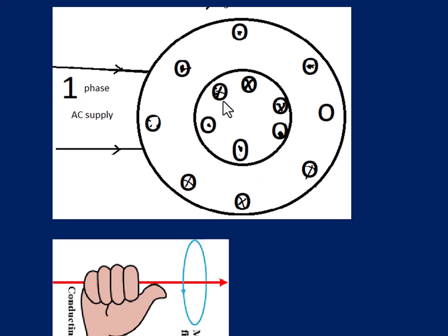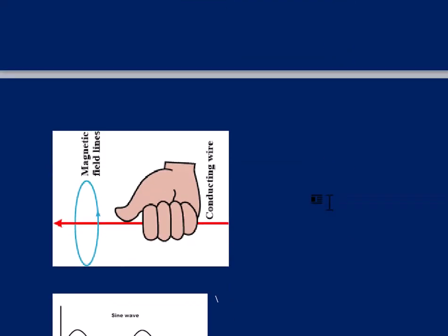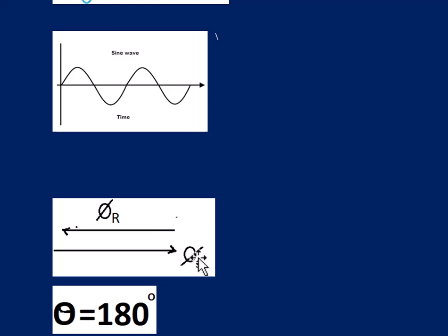Similarly, the same rule can be applied to the rotor: the top conductors carry the current into the paper whereas the bottom conductors carry the current out of the paper. Using the right hand thumb rule, the direction of the rotor magnetic field is from right to left. Shown vectorially, the stator flux and rotor flux have 180 degrees phase difference between them, so the net flux acting on the rotor is zero, and the rotor will not move — it is at standstill condition.